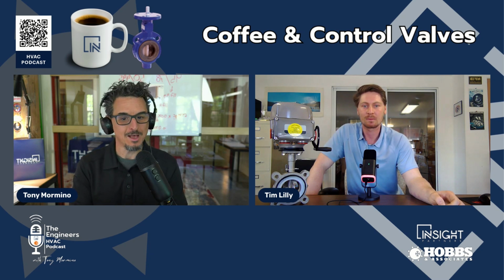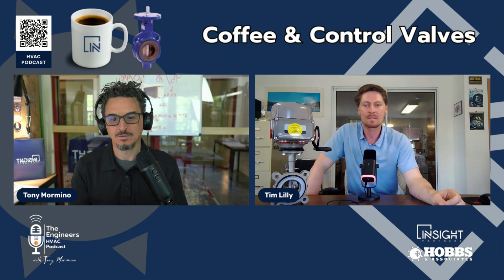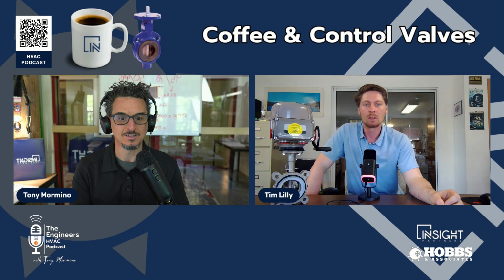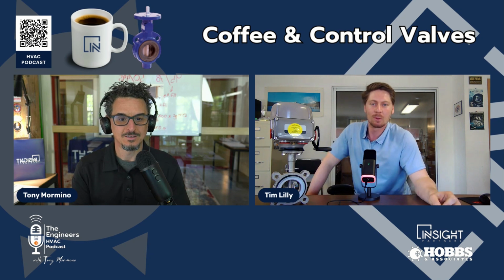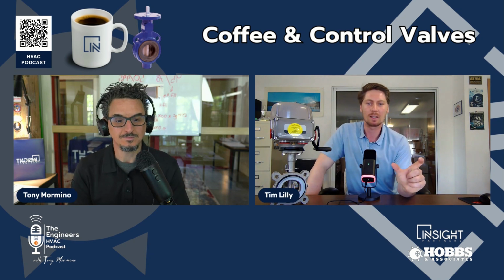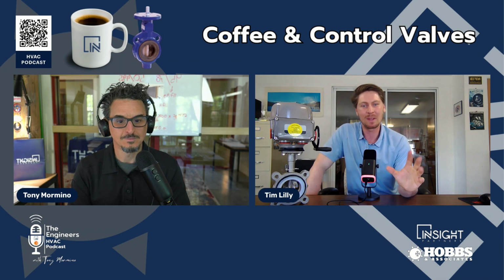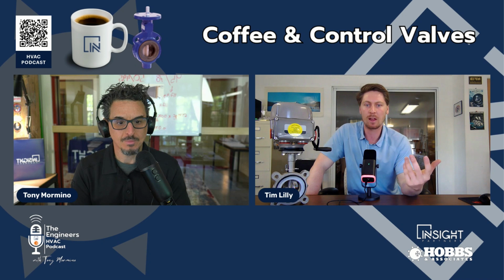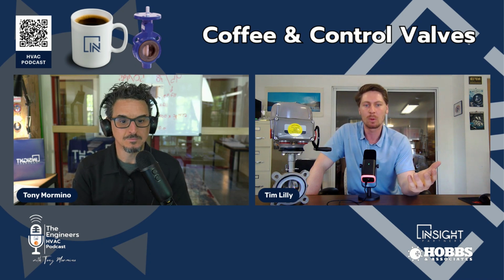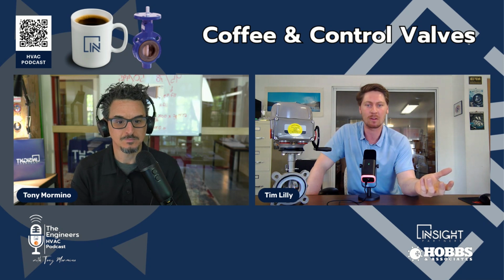Now, how many jobs percentage wise, like I've been working with engineers for a long time, but I don't handle the valves. So I don't know even what goes on. What percentage of jobs are butterfly valves versus ball valves? Is there, you know, a 10%, 20%, half are ball valves, half are butterfly valves, or what's been your experience? So it kind of depends on the size, Tony. When you have some of the smaller ones, like a 1 inch and below pipe, inch and a half and below, you see a lot of those characterized ball valves or even a globe valve. But when you get up to an 8 inch valve, you have no choice.